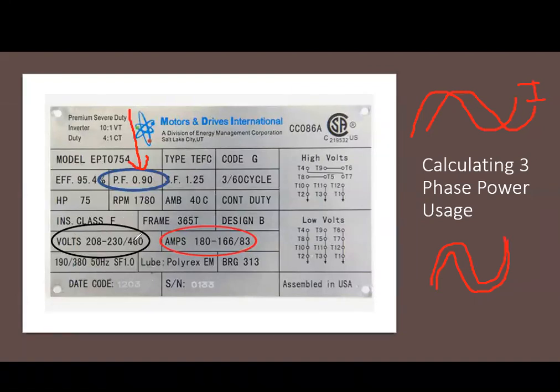But we also have to know the voltage that we're going to be using, which in this case would be the higher voltage, and how many amps we're going to use, which in this case would be the lower amps. When volts goes up, amps comes down. And so now that we know that we're going to be using 460, 0.9, and 83, the only number we have to include with this would be our 1.73. And we can calculate how much it would cost to run this motor, which is a large motor. It is a 75 horsepower motor. So this motor is going to weigh a little over 1,500 pounds. So we know it is a large motor.